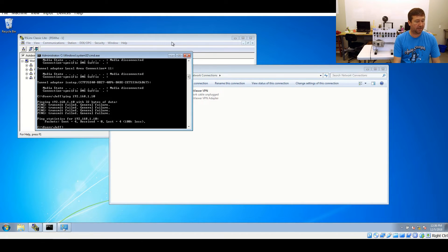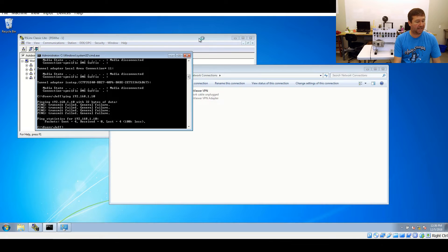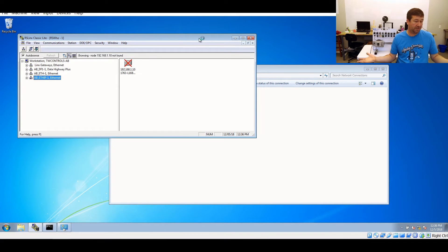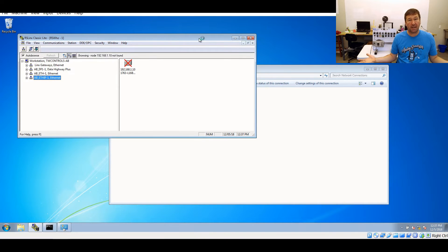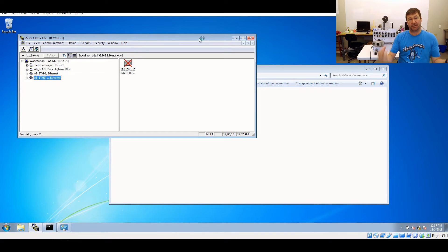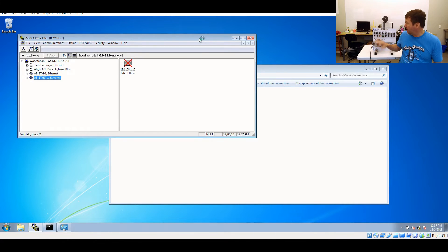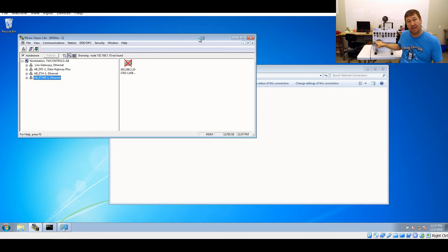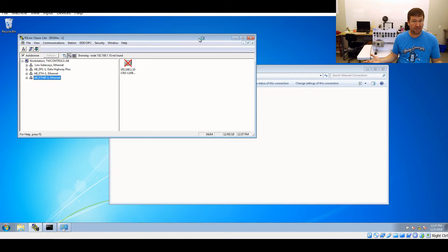We can see we're gone. So now, we're going to go back to our AB Ethernet IP driver, which should be showing something. We still have a red X. So in this case, we do have an IP address set on our PC, and we have an IP address set on our PLC, but pretty much, they're not on the same street.